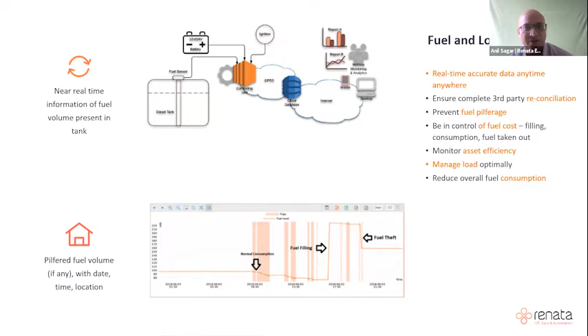You can also put up level sensors in fuel tanks if you're using fuel for DGs, or any kind of liquid - water, or any chemical used for processing your products. You can put up level sensors and see the level in real time, how the consumption is happening, how the filling is happening, and how the pilferage is happening. That can be linked with the efficiency of the equipment using that chemical or fuel, and it can be done remotely as well.